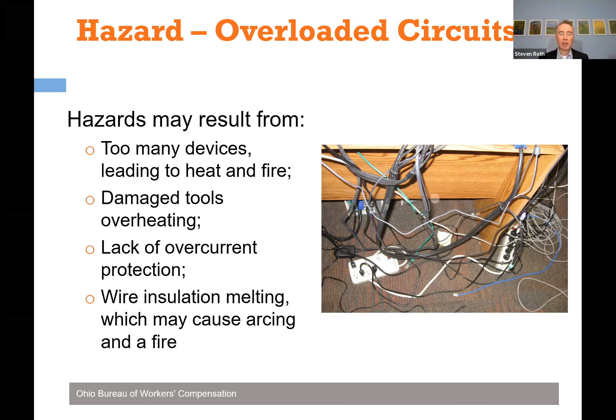A power tap must be used in accordance with its label and listing, which says it has to be plugged directly into an outlet receptacle—you can't daisy-chain it into an extension cord or another power strip. It's got to be plugged into the wall. That's how they've been approved to be used, and label and listing is critical—everything has to be used in accordance with it.